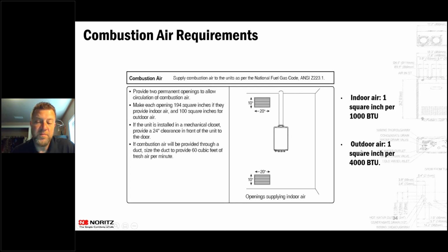So if you're pulling combustion air from outside of the house, say you're using a louver, or you're using a combustion air run that's coming into there, for every 4,000 BTUs with outdoor air, you need 1 square inch if you're using a big louver like this. Same thing if you have one of those big 8-inch pipes coming into that mechanical room: you need 1 square inch per 4,000 BTUs of the unit that you're using.